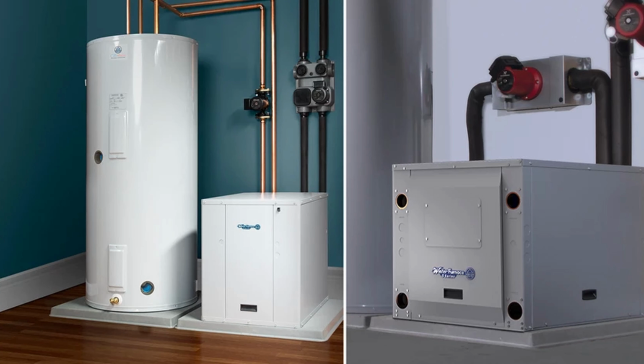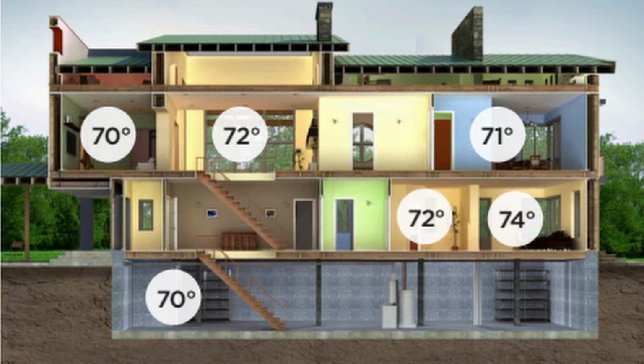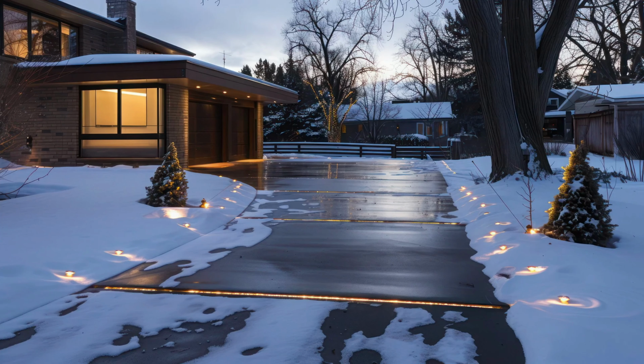For the geothermal system, I'd go with a Waterfurnace 5 Series that's perfect for a water-to-water application. It can handle heating the hydronic floors and produce domestic hot water. However, I'd still probably want to include an electric backup heater for those worst case scenarios when the geothermal system might underperform. Luckily, there are electric heater add-ons available. Waterfurnace systems can also be zoned, which is great for areas of the home that need different temperatures, like upstairs rooms or basements. Plus, we can even add hydronic underlayment to the driveway and melt the ice and snow.